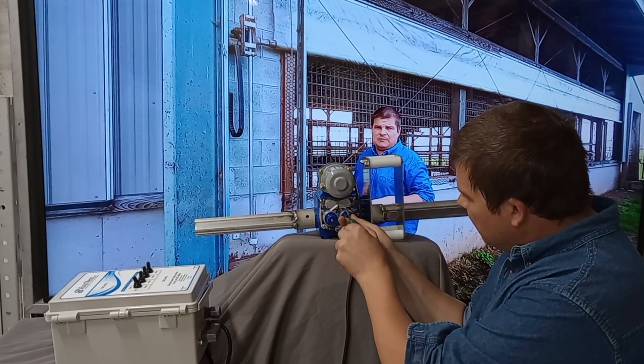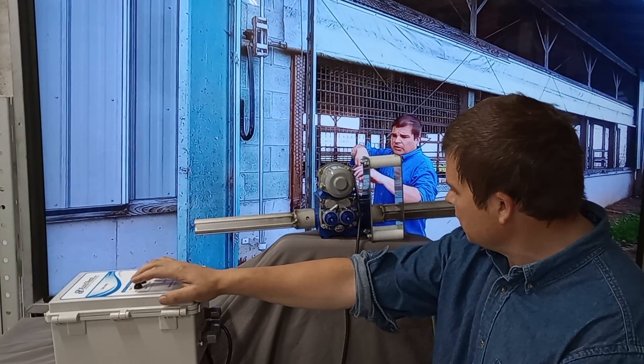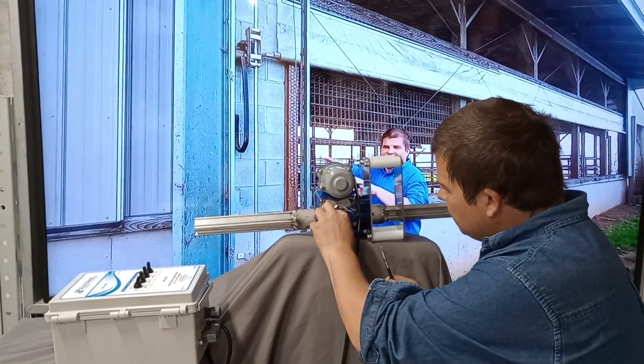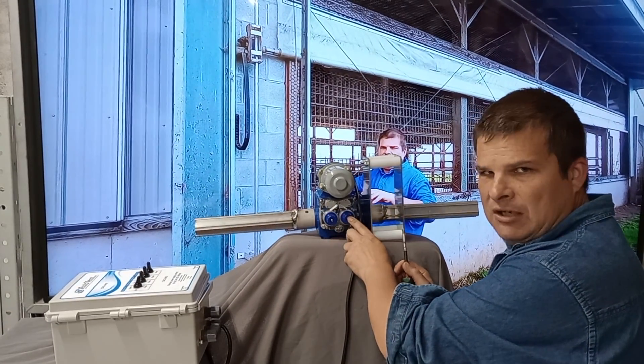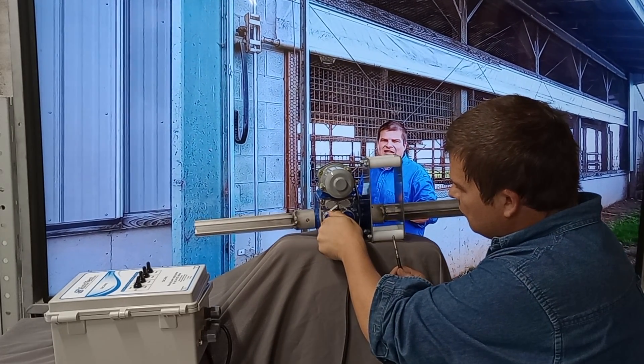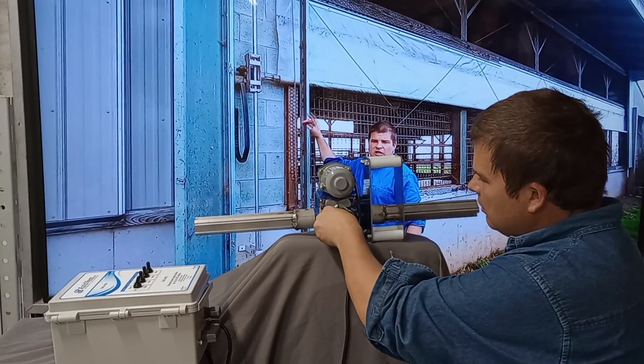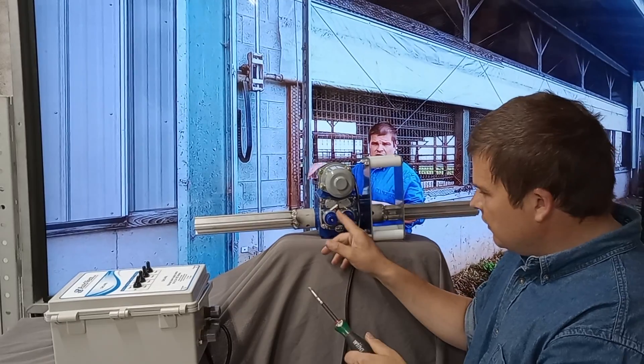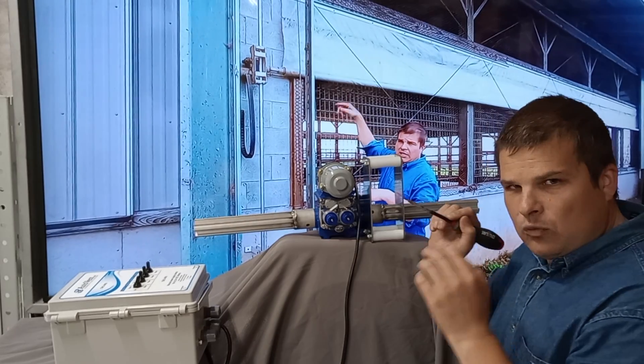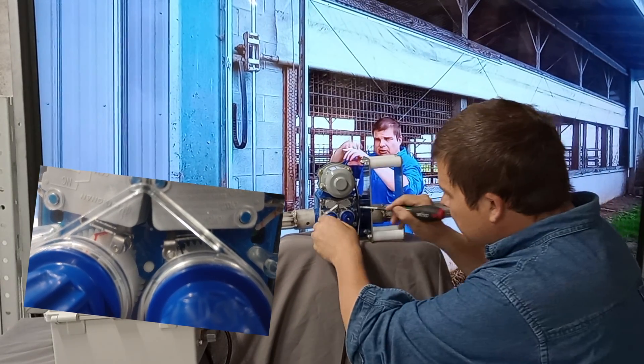There are little cams right in there. It stopped because we had it set just so. Now we're going to go the other direction — going up again. This little red dot is your top limit, this is your bottom limit. If I turn this, that stopped it. I can adjust it again and it started again. So this knob adjusts a cam right inside there. There are switches; when the switch hits the cam it turns off the motor, and you can look in and see it.